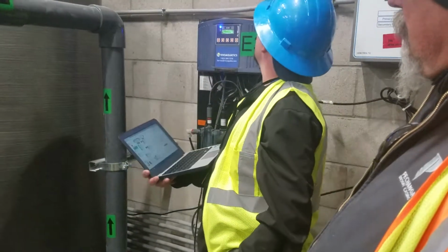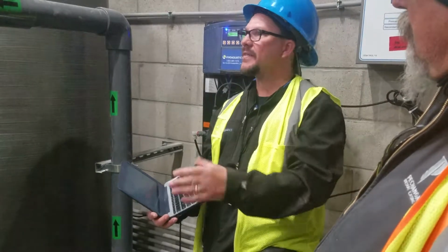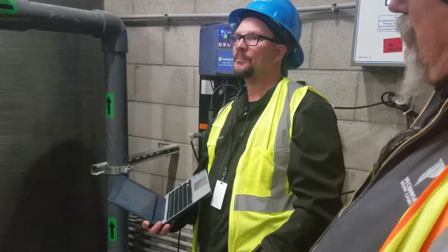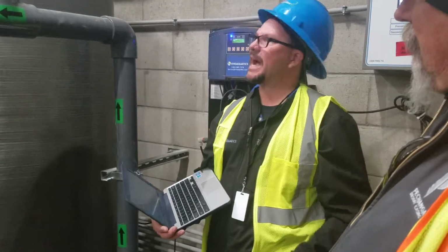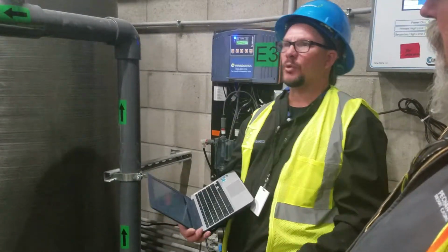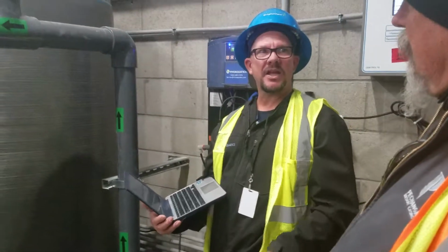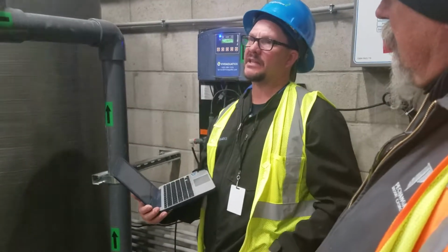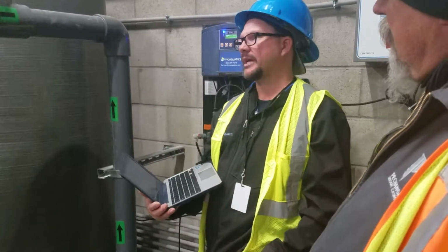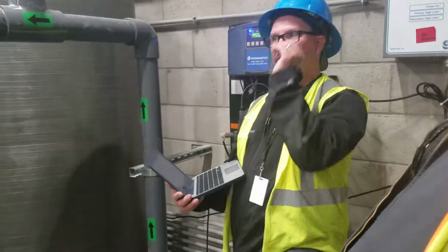So 7.3 is not where we want it, but as you said, if we start feeding chlorine in there, that pH is going to come up on its own. The thing we want to be careful of is the alkalinity. Keep that alkalinity dialed in, chances are your pH will always be good. So when you're doing your testing in the morning, midday, afternoon recommended, make sure you're getting your alkalinity test in there as well, not just pH and chlorine. I already let them know with the CO2 alkalinity is going to be important.